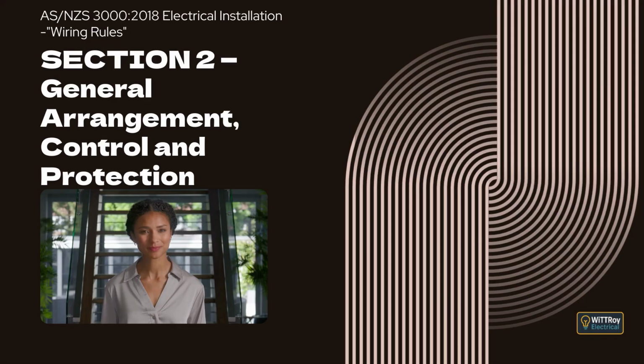If equipment contains live parts from more than one supply, there must be clear notices warning people that different supplies exist. These warnings help anyone working on the equipment identify which circuits must be isolated. The only exception is when an interlocking arrangement guarantees that all circuits are isolated, or when the live parts are safely covered so accidental contact is not possible. Where needed, the installation must also provide a way to discharge stored electrical energy before work is carried out.